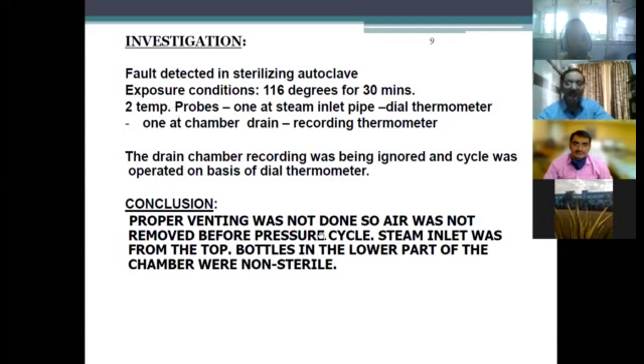The dial thermometer was showing the right temperature, and the cycle was operated on that. After the cycle was over, the injections were removed, thinking everything is sterile. But the other sensor in the drain chamber was ignored, and because of that, since proper venting was not done, air was not removed before the pressure cycle. The steam inlet was from the top, so the bottles in the top part of the autoclave were sterilized, while those in the lower part of the chamber were non-sterile.